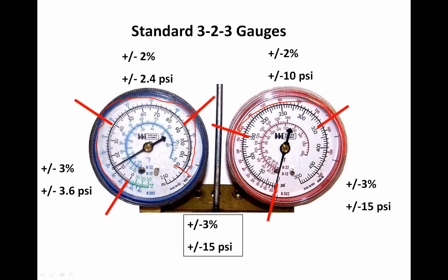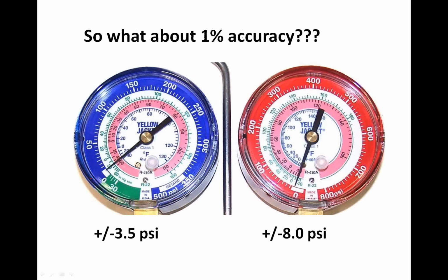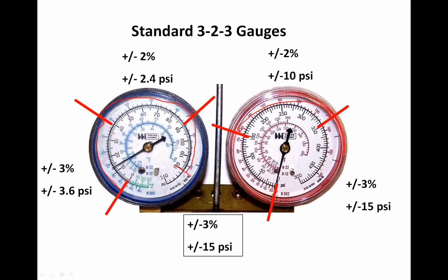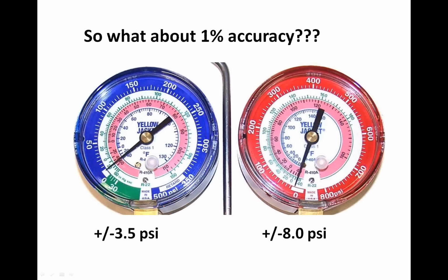Now, if we're outside of that center of its span, we're at plus or minus 15 psi, and that's quite a bit of difference there. So, just keep these numbers in mind for a second. Well, one of the grand things the industry did was they said, you know what, we're going to get away from these 3-2-3 gauges. We're going to go to a 1% accuracy gauge. Well, follow this for a second, because 0 to 350 is the span of the gauge, right? 0 to 350. Well, what's 1% of 350? It's 3.5 psi. So if you go back here for just a second, we're at 2.4 psi. We went to 3.5 psi. We actually lost ground on this 1% accuracy low side gauge.